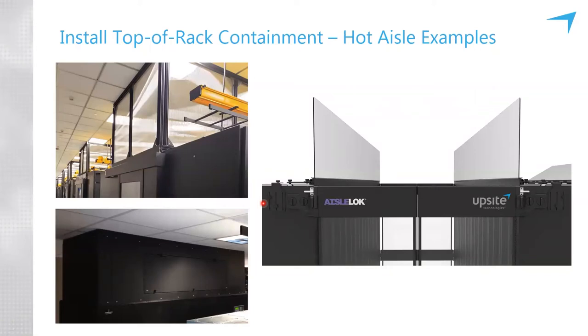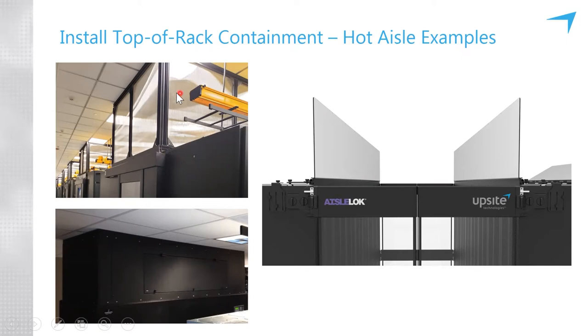Hot aisle containment means building a vertical perimeter around the hot aisle from the tops of the racks to the ceiling. Hot aisle containment is most often used in scenarios where you have an overhead return plenum above a drop ceiling — as seen in the photo at the top left. There will be perforated or registered tiles in the ceiling instead of solid tiles. The hot air fills the hot aisle, rises, and is drawn back to the intake of the perimeter air conditioning units.